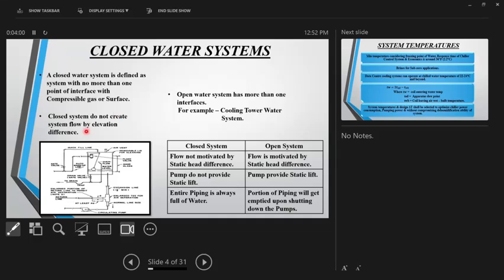Now that transfers a few theories. You can also deduce that closed systems do not create system flow by elevation difference. Imagine a chill water system of a 30, 40, 50 storied commercial building. If you switch off the pump, there is no way that there is a flow, correct? The flow will be established only when the pump runs. So even though we are talking about a 200, 300 meter tall chill water structure, unless the pump runs, there is no way that the water will flow. So in closed water systems, flow is not created by elevation difference.